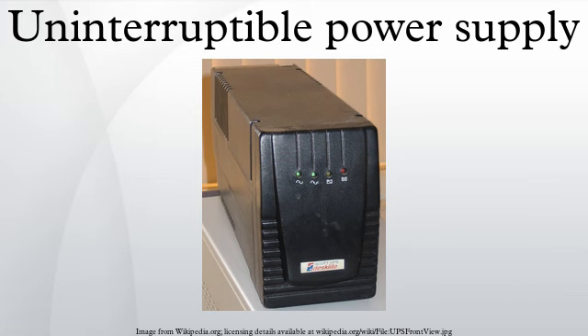A laptop computer is a classic example of a PC with a DC UPS built-in. High-voltage DC is finding use in some data center applications, and allows for small power conductors, but is subject to the more complex electrical code rules for safe containment of high voltages.